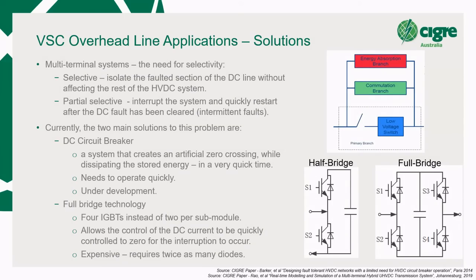So there are basically two. I've got a little comment up there about multi-terminal systems, and it's basically saying the consideration of how you handle the DC side currents during faults is particularly important for multi-terminal, because you want to work out, do you keep one line operational while the other one is unaffected? But I won't really go into that. The point here is there are two main solutions to the problem that are being discussed in the international community right now. It's the DC breaker and there's the full bridge.